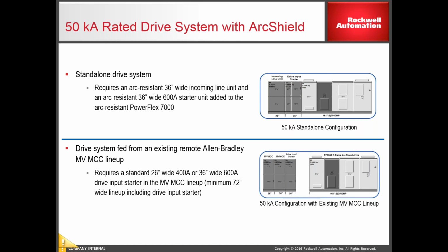So with the 50 kA rated drive, the incoming line, you have to have an incoming line unit, and it has to be 36 inches wide, and the drive input starter has to be 36 inches wide as well. And that will get you the 50 kA rating for standalone configuration.